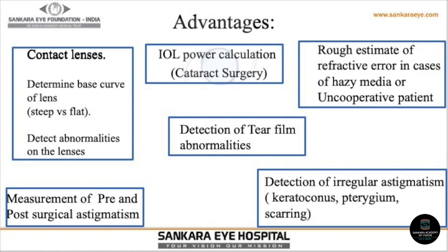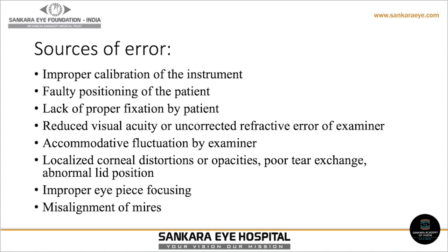The pitfalls of the keratometer include: improper calibration of the instrument, faulty positioning of the patient, lack of proper fixation by the patient, localized corneal distortions or opacities such as in severe dry eye, improper eyepiece focusing, and misalignment of the mires.